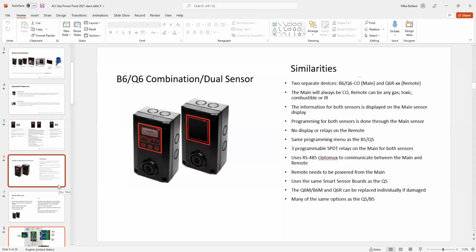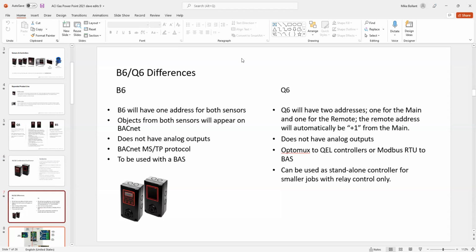The one thing I think I forgot to mention on the BACnet is that there's one addressable point. Is that correct? Yeah. By going to the next page, we'll give the differences between the two. Here's basically the difference between the two. The biggest difference is on the BACnet side: there will be one point that's addressable, not two, for both sensors. So that makes a big difference on your end. Instead of, say, 32 sensors coming on the BACnet protocol giving you 64 addressable points, you'll have 32 for both the CO and NO2.